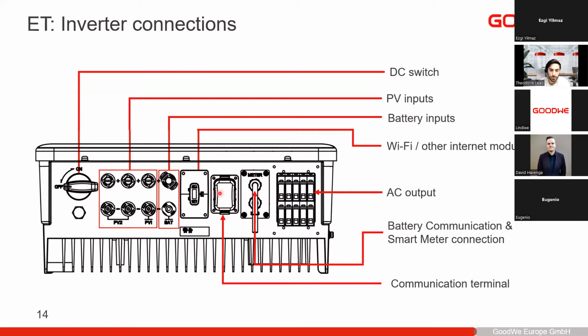The new ET inverter, called the ET Plus, looks like this. It also has a dry switch, which is basically 2 pins that go out of the inverter, which you can activate on and off based on settings in the inverter. You can set it so that if it produces more than a certain amount of energy, it activates this switch. Some devices, for example heat pumps, have a connection where you can connect the switch, and then you can control some loads based on the PV production.